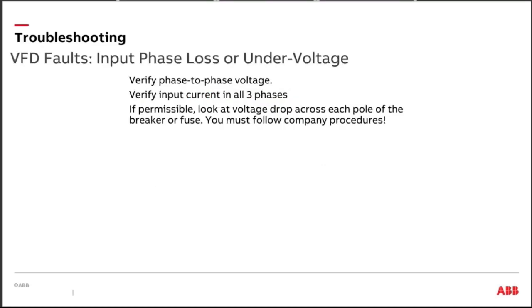Input phase fault, a very common thing. Just kind of look and make sure that you've got all three phases coming in. Now, one of the really cool things about the ABB drive, we might not necessarily trip on input phase fault if we have a momentary input phase fault, because we're not stressing the DC bus of the drive. That's a nice thing. Think about it like this.